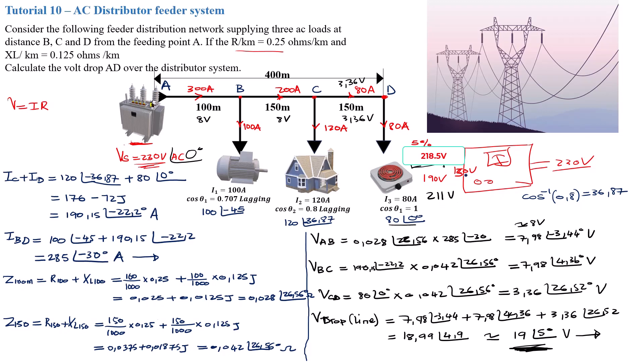So 211 volts is way below the five percent acceptable range. This is an alarm. An alarm needs to go off because this cannot be accepted. You will need a voltage stabilizer to continue to live in this street here, otherwise you need to call your energy supplier, your Eskom, your power distributor to come and fix the problem in this line so that your house can have stable electricity.